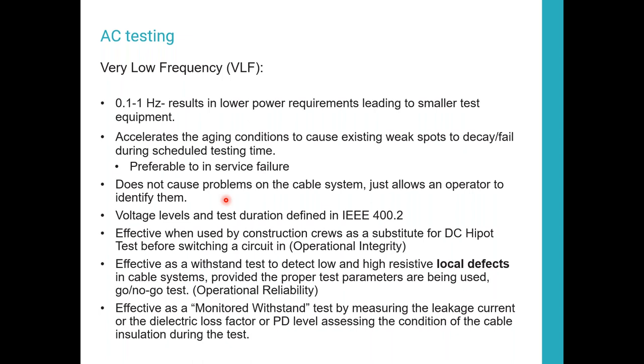And once they know where that PD starts at, they can compare it to the operating voltage, your normal operating voltage, your nominal voltage. If the voltage is well above your operating level, it's not a concern because you're never going to get to that point. If it's really close to your operating level, now that's where you want to identify some characteristics of it. Say, okay, my insulation's withstand voltage is now getting closer and closer to my actual operating voltage level, and I've got a problem that I've now got to address.